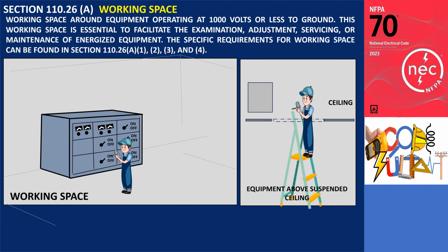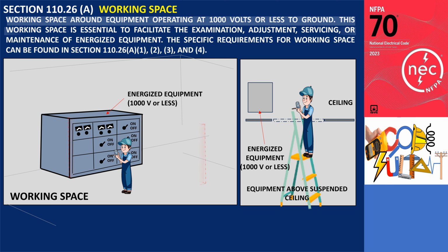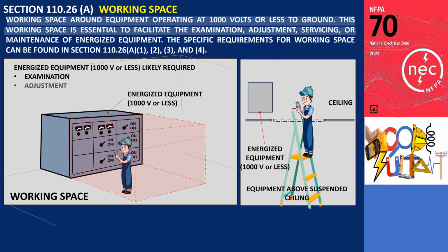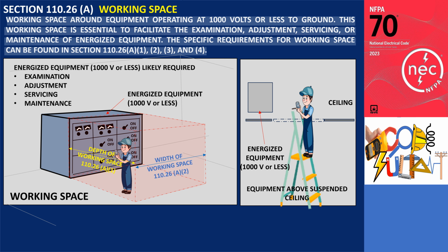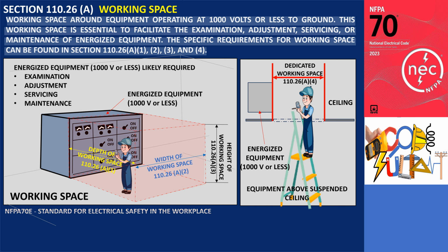Section 110.26(A) of the applicable regulations provides guidelines for the necessary working space around equipment operating at 1000 volts or less to ground. This working space is essential to facilitate the examination, adjustment, servicing, or maintenance of energized equipment. The specific requirements for working space can be found in Sections 110.26(A)(1), 110.26(A)(2), 110.26(A)(3), and 110.26(A)(4).